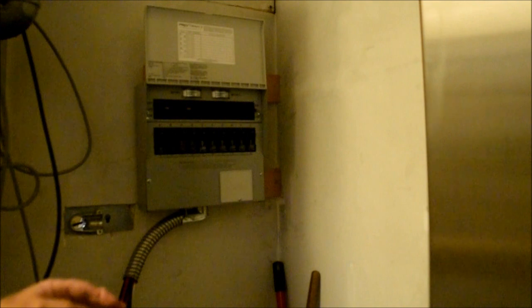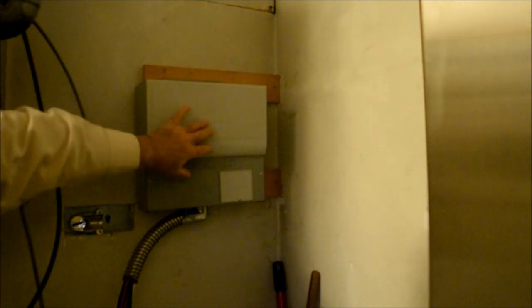So what I've done so far is I've mounted the transfer switch on the wall. Now this little thing is fairly heavy. It weighs the better part of 20 pounds. So I didn't want to just screw it to drywall using drywall anchors. So what I did was I put a couple strips of one by four up here and down below that I screwed into studs using two and a half inch screws, and then attached the transfer switch to the wood strips. So that is solid now. It's not going to come off there.